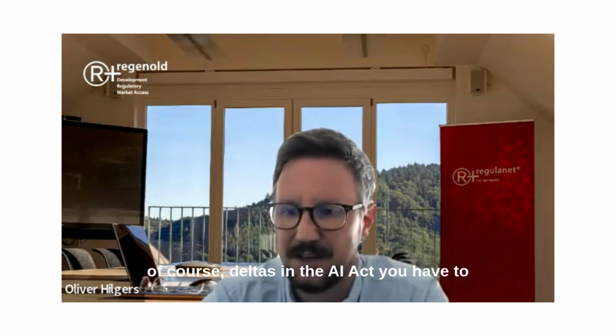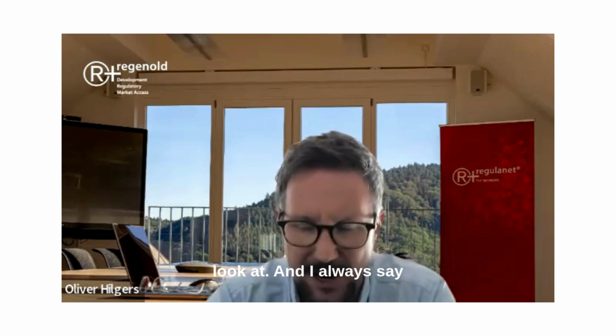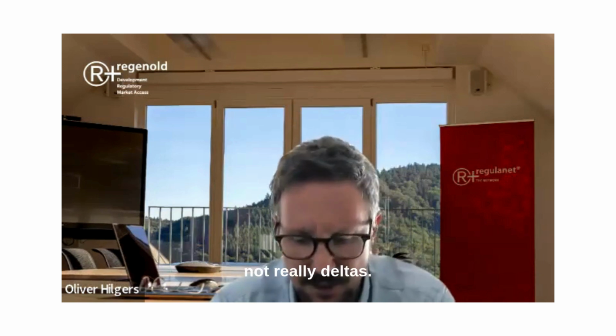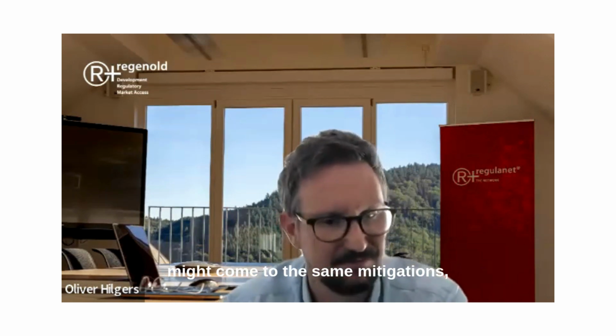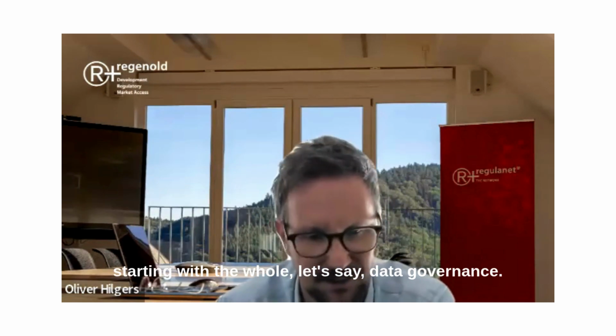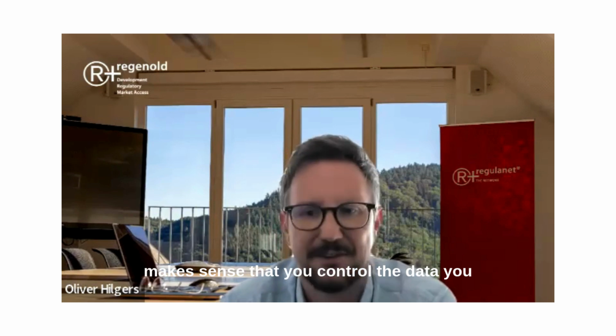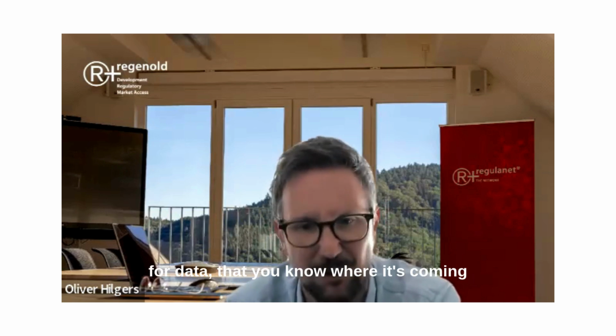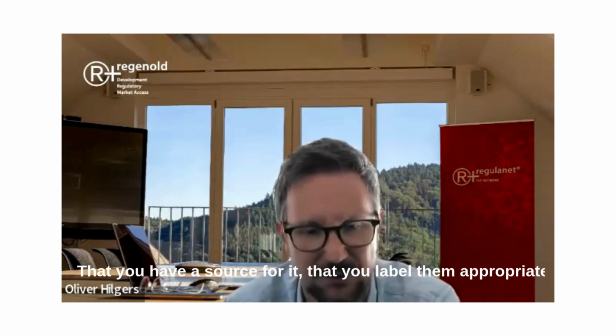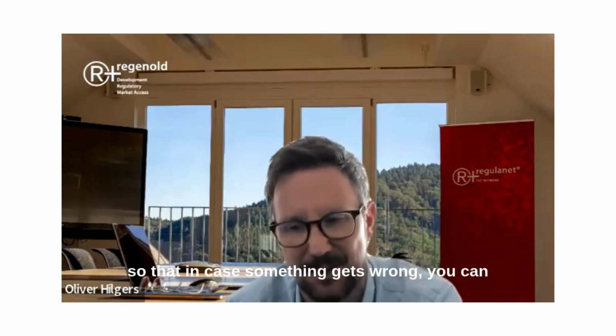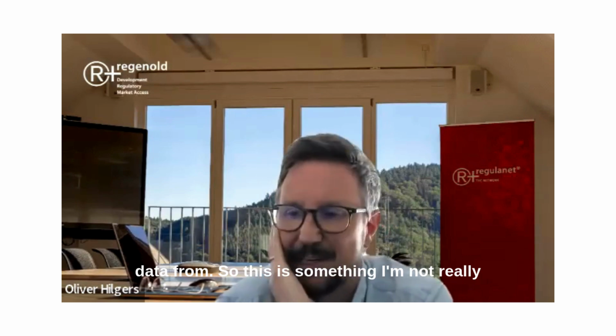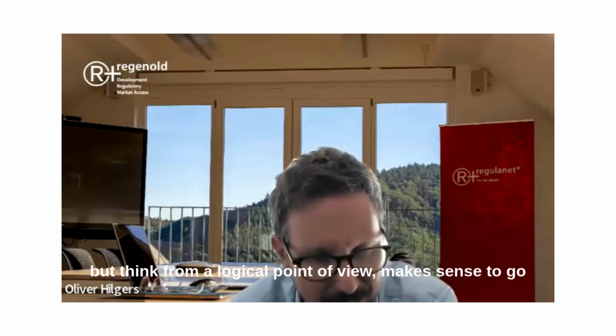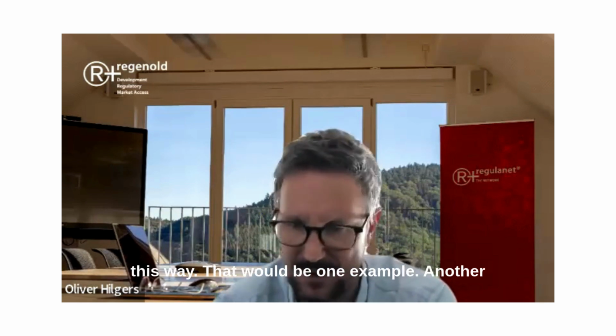There are, of course, deltas in the AI Act you have to look at. And I always say, the deltas are very often not really deltas. Depending on the risk of an MDR product, you might come to the same mitigations, starting with data governance. To me, regardless of the AI Act, it makes sense that you control the data you use for training, that you have version control for the data, that you know where it's coming from, that you have a source for it, and that you label it appropriately, so that in case something goes wrong, you can trace back what the problem was and where you got the data from. Although it's not directly addressed in the MDR, from a logical point of view, it makes sense to go this way. That would be one example.